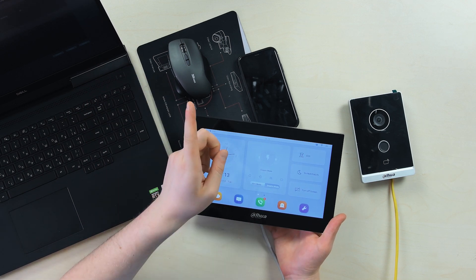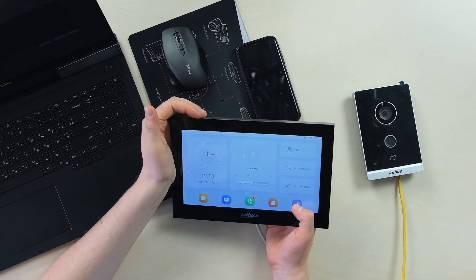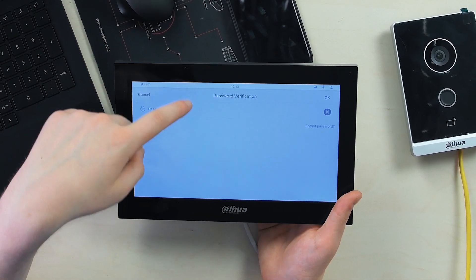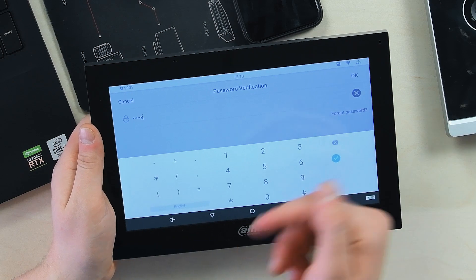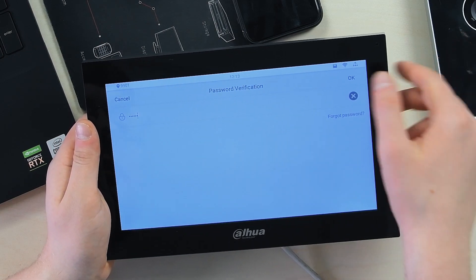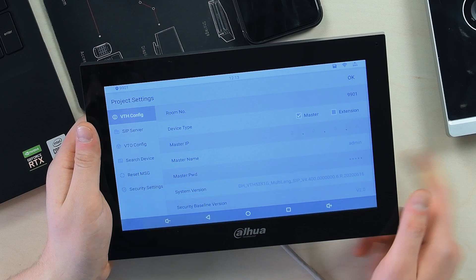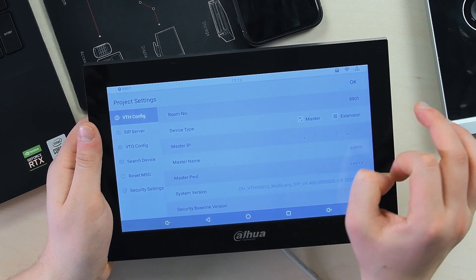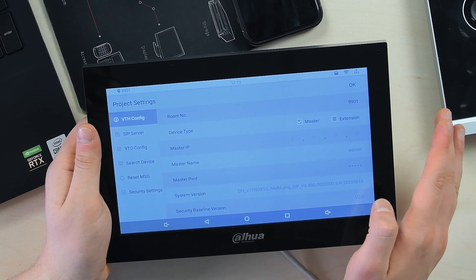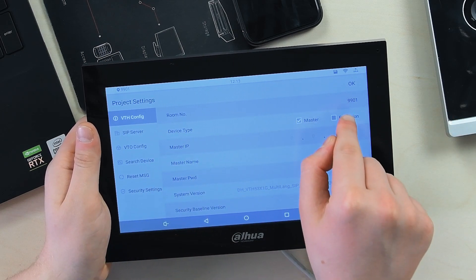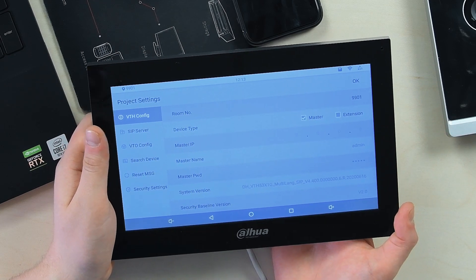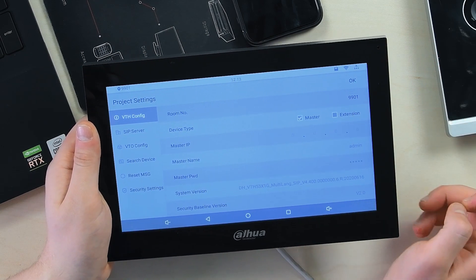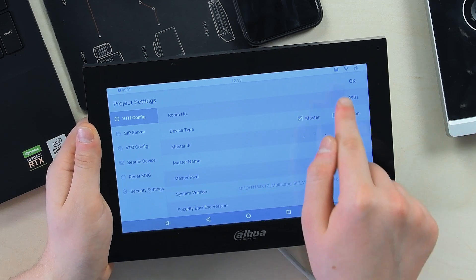Now we need to access the admin settings and this is a long press on this button. We got it. The password we've created during the activation stage on the monitor, it's gonna be different from that one. There's a default that happens all the time on the Room Number: 9901, but it could be other numbers, it could add symbols in the end. It has to be four digits like this. Then press OK and you're good.